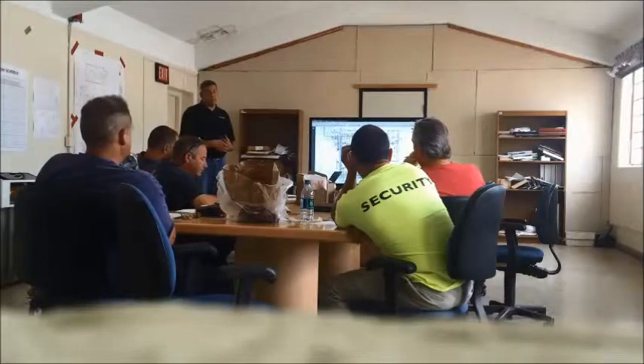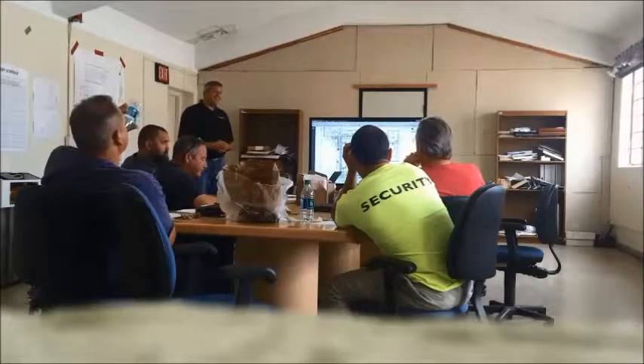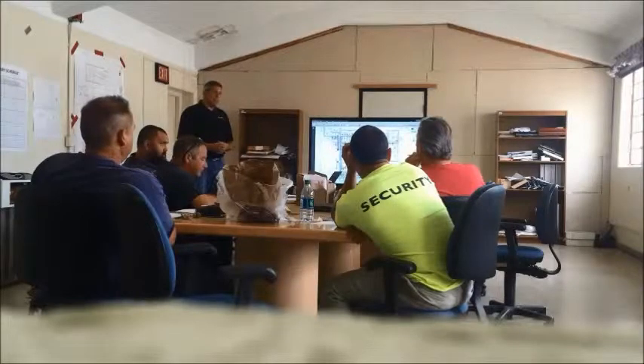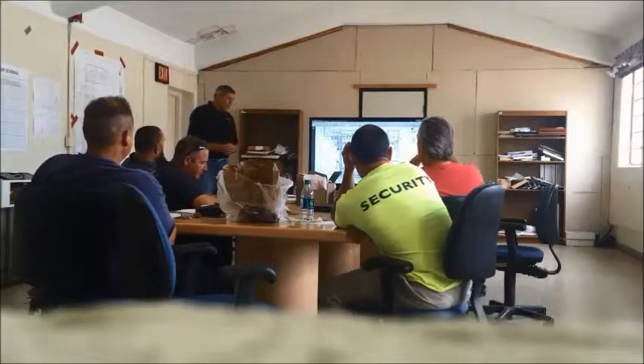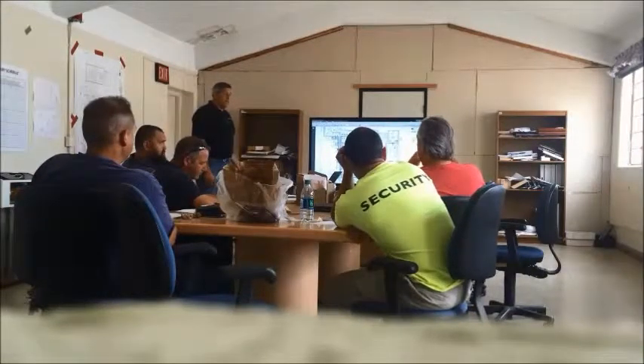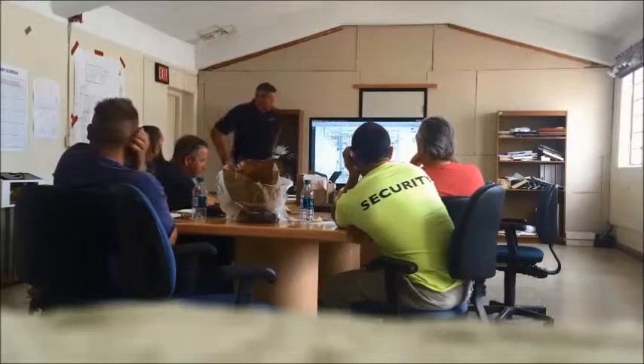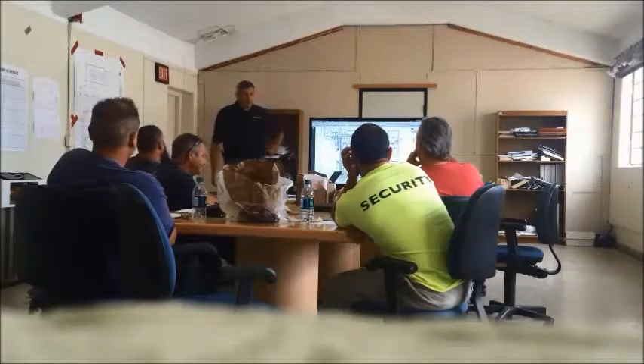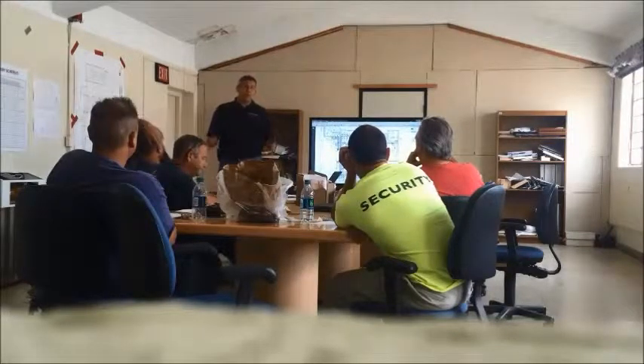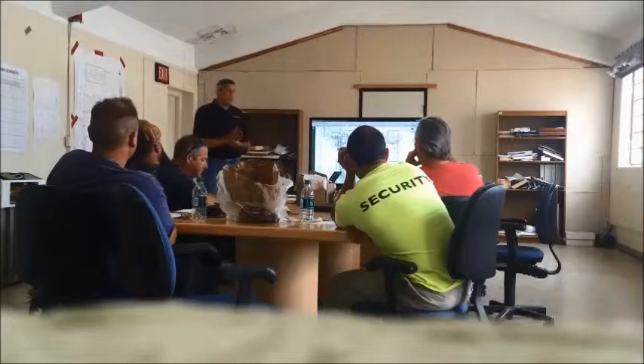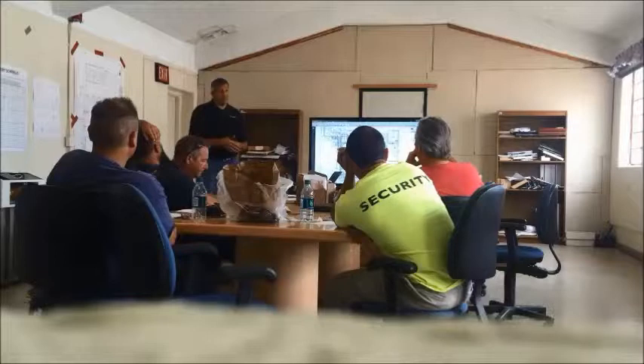So this is a little pet thing of mine, and the pet thing of other people's too, is the temperature of domestic hot water. I agree that 140 is good, but there's a lot of talk about 120, can't go above 120, so I guess this project was spec'd out at 140, and that's okay. What we have is 140 in the hot water generator, but then we have a TMV, TMV-1, we're talking more on the plumbing side this afternoon, after our lunch break, that provides 120 degree water to the majority of the fixtures.